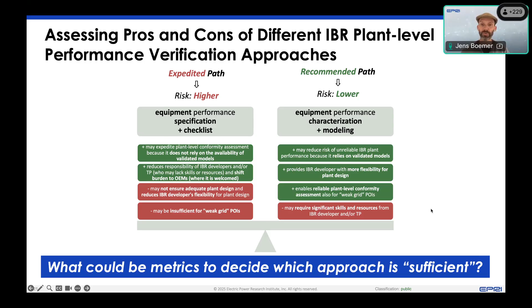So comparing what this means in terms of the process, you may remember I showed this slide for the model-based verification last time. We can probably apply something similar here for documentation-based verification. It seems to make sense to review OEM documentation showing compatibility of IBR equipment and reviewing developer or generator owner documentation describing how the anticipated IBR plant design would address 2800 requirements early on in the process to create some confidence in the expected plant performance, whereas then towards the end of the process, a more detailed review specifically of any changes in that documentation seems to help addressing partial conformity with the standard. And with that, I believe I'm through. Thank you so much.